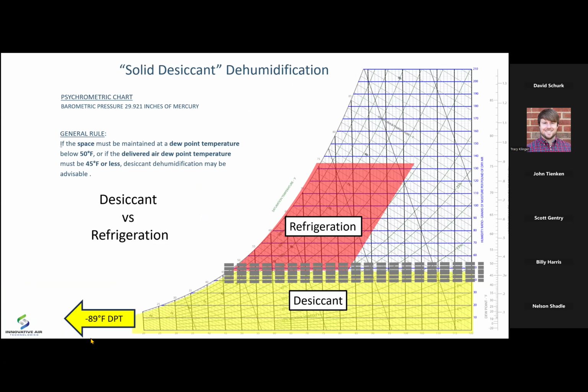So I show a psychrometric chart, and I show where desiccant dehumidification plays, where refrigeration, cold coil systems play, and this gray area between the two. There's always a gray area. So let's unpack this a little bit. Here's my general rule. If the space conditions need to be maintained at a dew point temperature below 50 degrees Fahrenheit, what's that mean? Here is a 50-degree dew point temperature right at the top of this gray line. We see 50 on the left-hand side. We see 50 on the right-hand side. That's a 50-degree dew point.